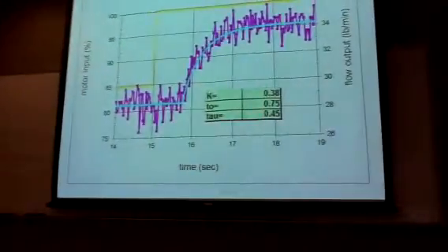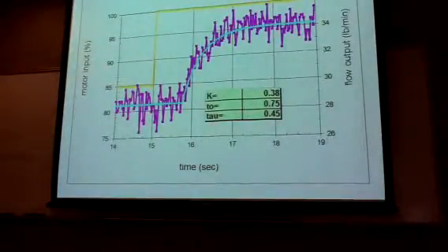Here's some results from our modeling. This is from 85 to 100%. This is just one example. So here we have a K of 0.38, which is very comparable to the previous that we got from the graphical checks. And the same with the dead time and the time constant. And it's pretty close from the template we used. It matches the curve pretty well.